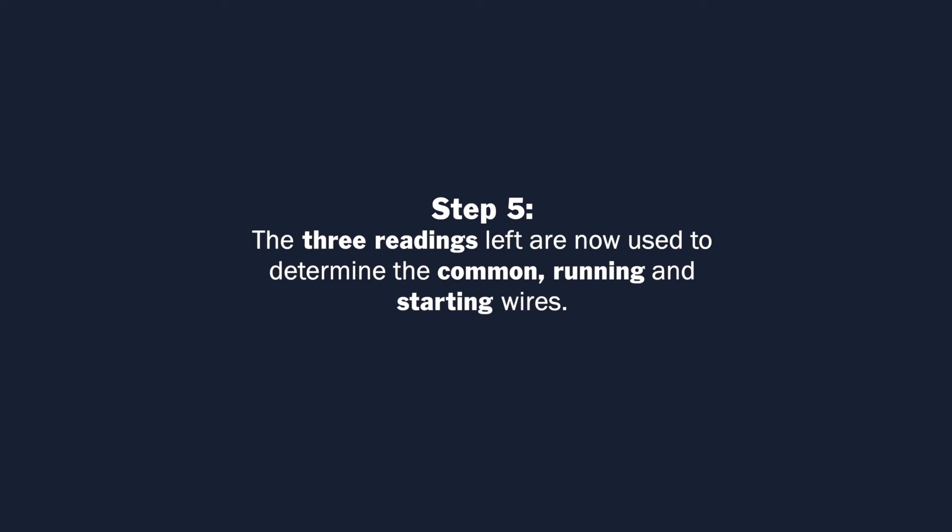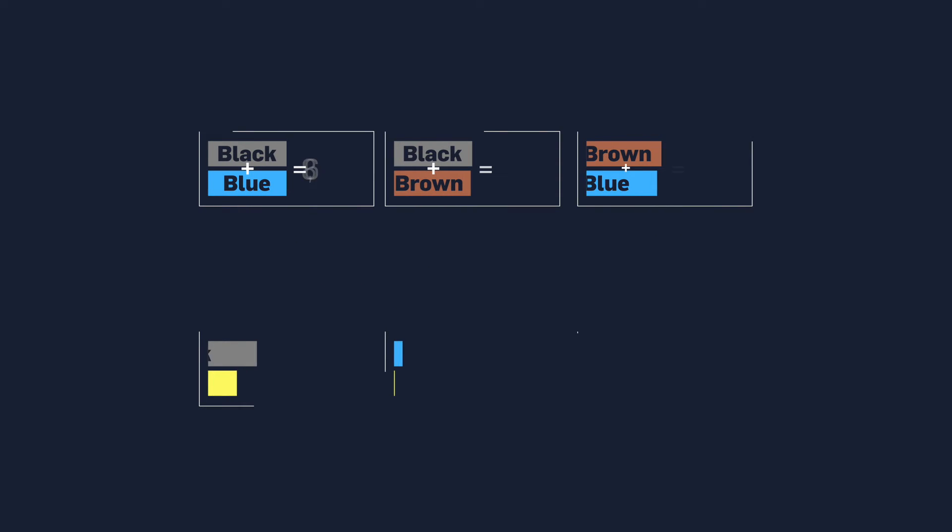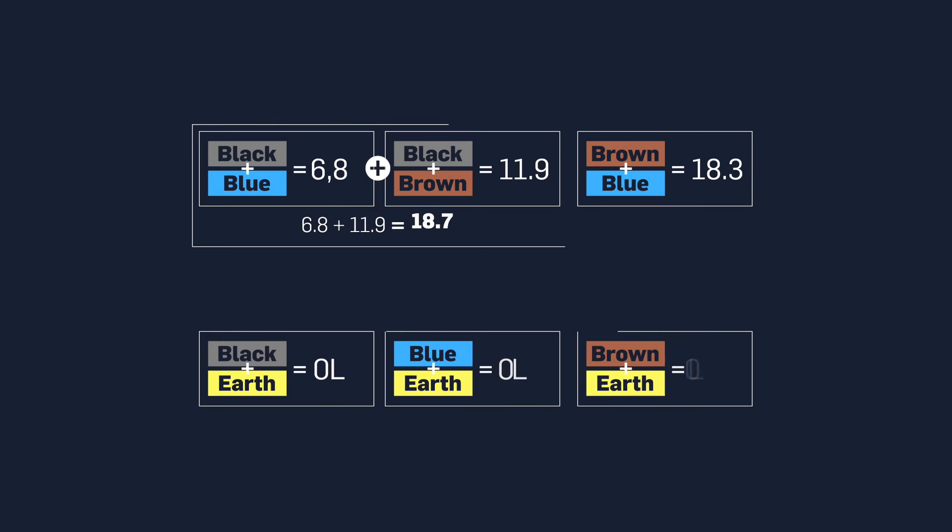Step 5. The three readings left are now used to determine the common, running and starting wires. If the two lowest readings are added together, then a value that is the same or higher than the highest reading should be obtained. The difference would be greater for longer cable lengths. Note the wire that is present in both of the two lowest readings. This is the common wire. Note the other wire present in the lowest reading. This is the running wire. Note the other wire present in the second lowest reading. This is the starting wire.